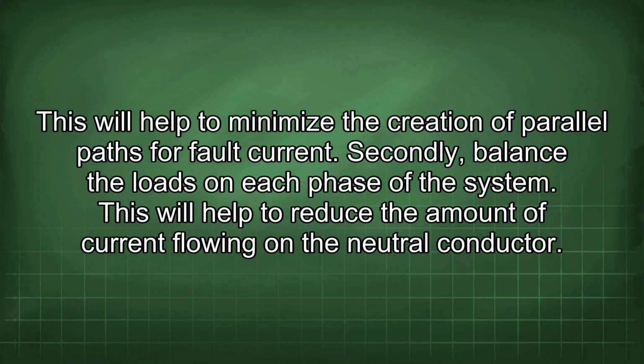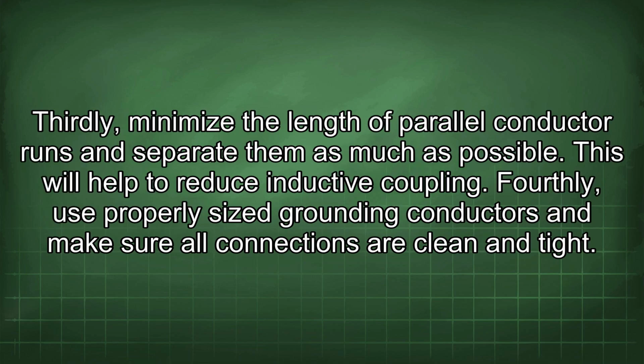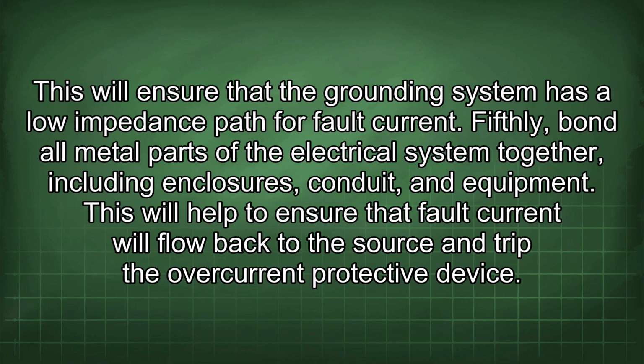Secondly, balance the loads on each phase of the system. This will help to reduce the amount of current flowing on the neutral conductor. Thirdly, minimize the length of parallel conductor runs and separate them as much as possible. This will help to reduce inductive coupling. Fourthly, use properly sized grounding conductors and make sure all connections are clean and tight. This will ensure that the grounding system has a low impedance path for fault current. Fifthly, bond all metal parts of the electrical system together, including enclosures, conduit, and equipment. This will help to ensure that fault current will flow back to the source and trip the overcurrent protective device.